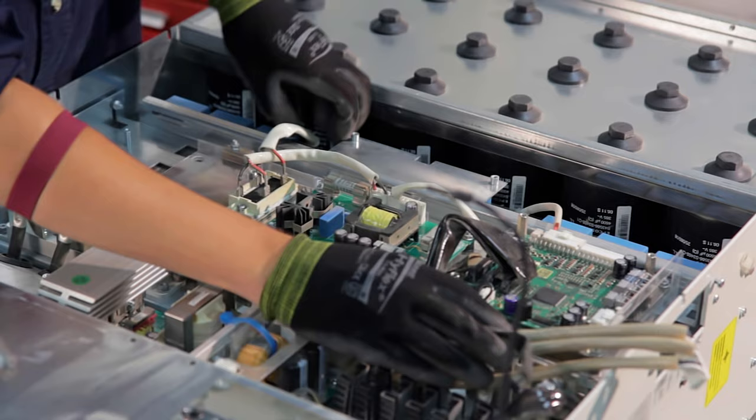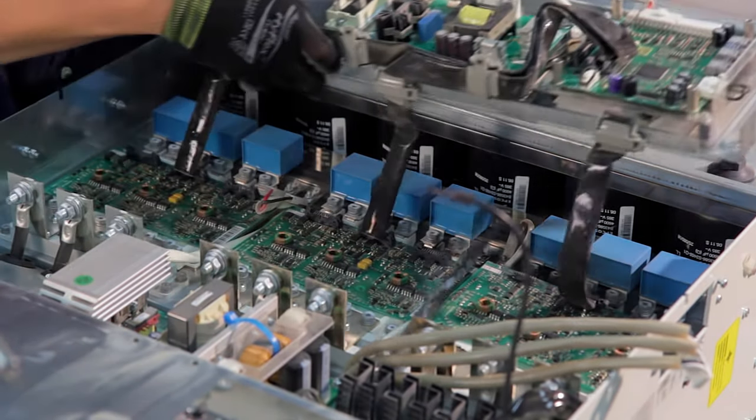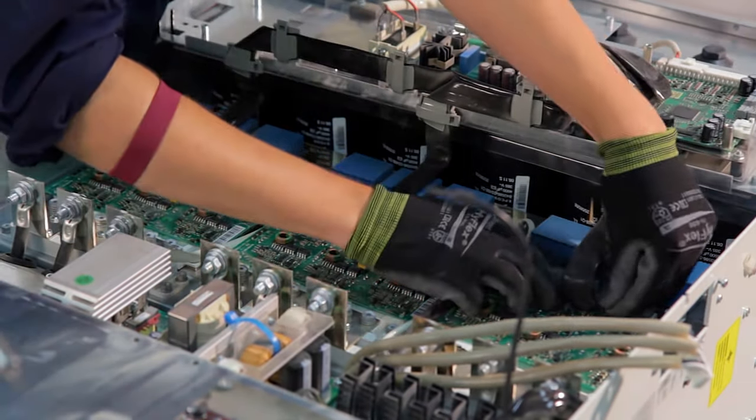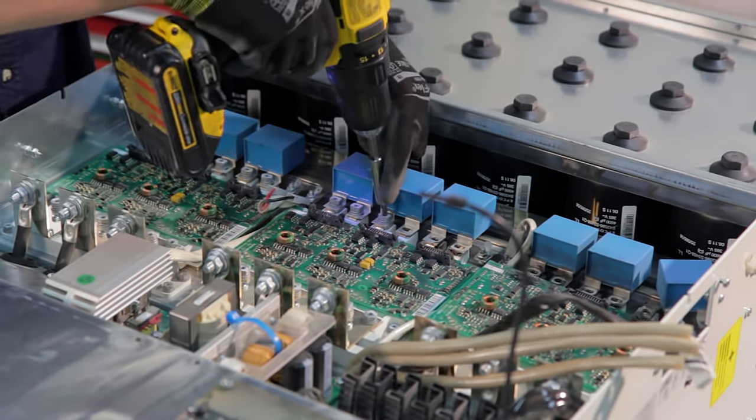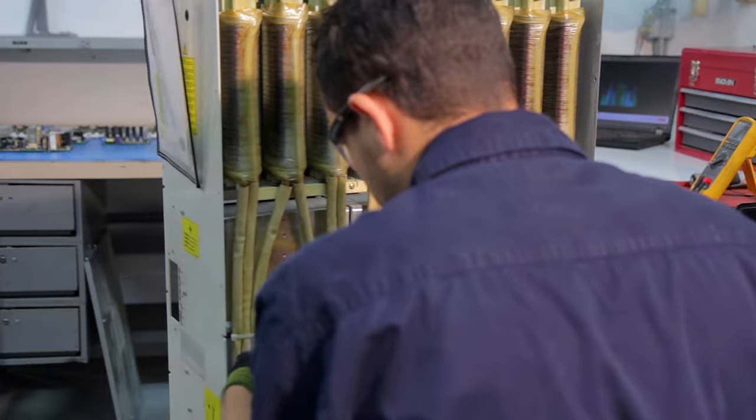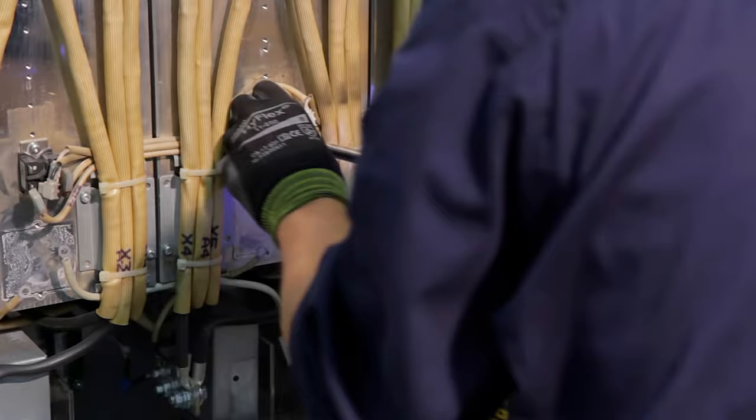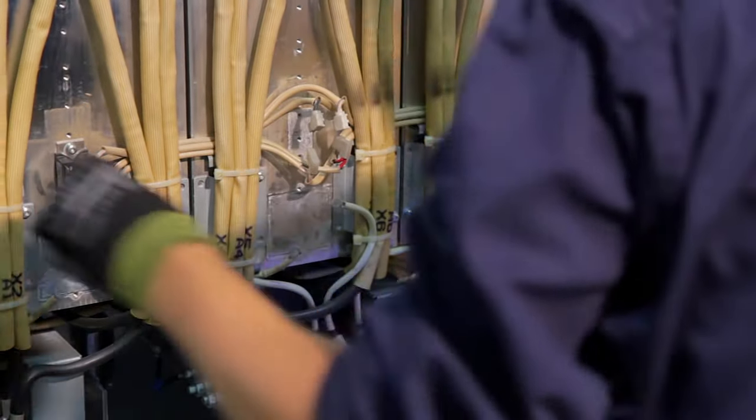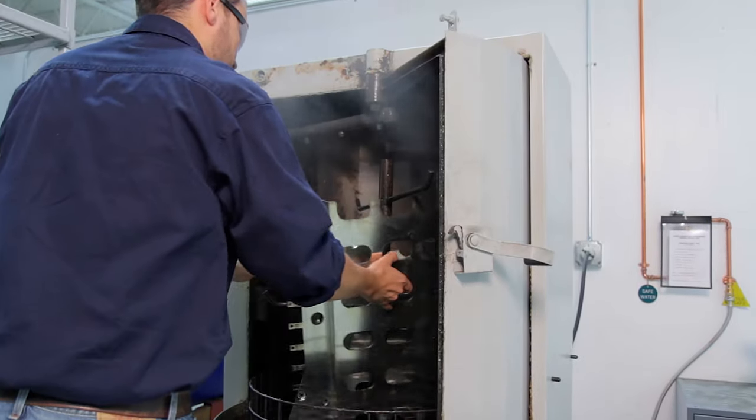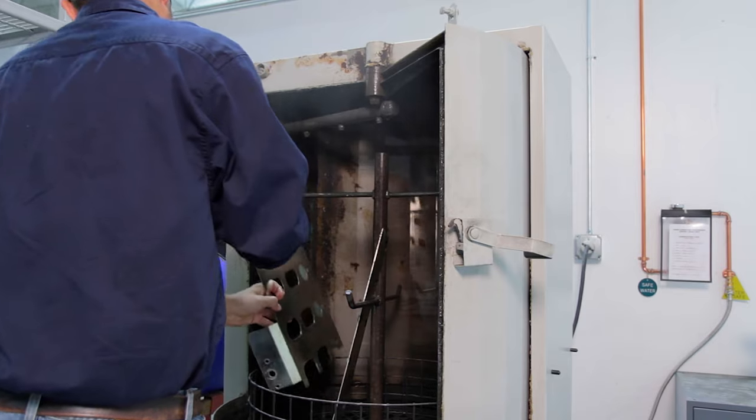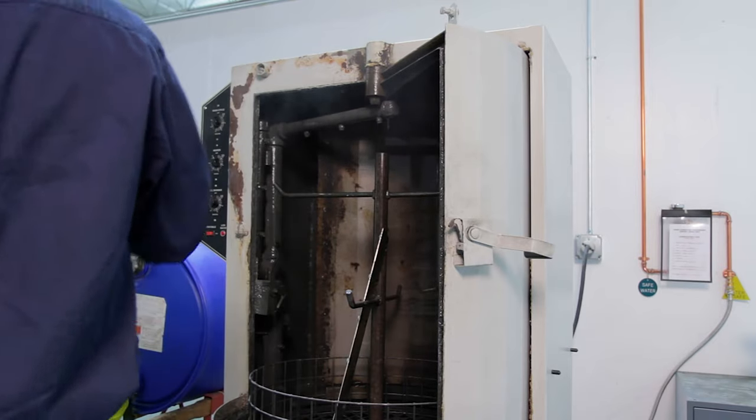After a full inspection and diagnostic testing, the drive is disassembled for cleaning. Chassis frame, covers, side panels, heat sink, and hardware components are washed with cleaning solution and water to remove any dirt or other contaminants. Ribbon cables are replaced and other cables are cleaned or replaced as needed, while PC boards are cleaned per ABB specifications.